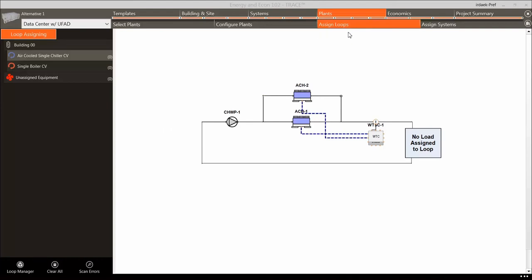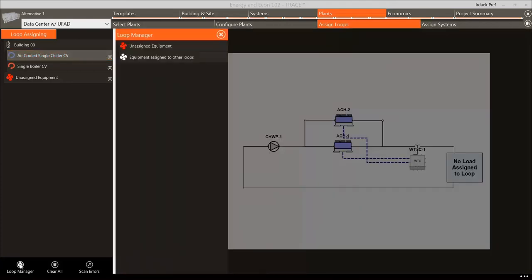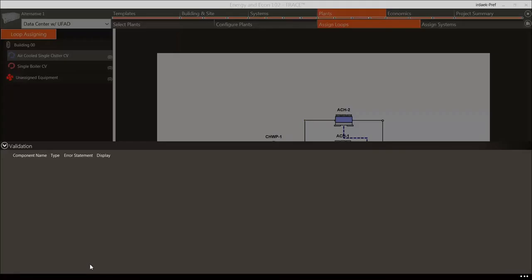The next section is Assign Loops, where users can assign loops to each other. For example, a water-cooled chiller rejects heat from inside the building to the outdoors by using a cooling tower, so the chiller must be linked to a condenser loop within TRACE. This screen is automatically complete if using a standard plant configuration from the plants library or plant wizard. Since we selected a pre-configured plant with only air-cooled chillers and a boiler, there is no need to assign anything. The Scan Errors button runs a validation check on this section, and the eye icon lets you view connections between loops.